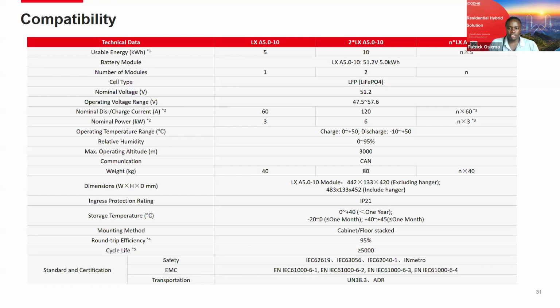Then apart from that, most of the specs are quite similar, apart from the discharging rates. So IP21, cabinet mounted, floor stacked. The battery comes with a bracket, 95% round trip efficiency, over 5,000 discharge cycles and the likes. The battery is also tested to certify it in transporting conditions and other testing codes or international testing standards that verify that the battery works okay and it's safe for use.